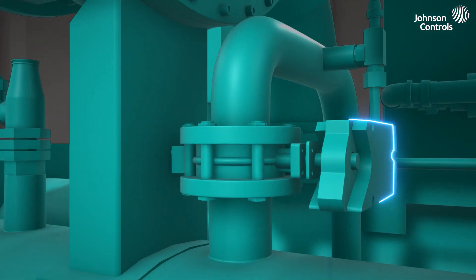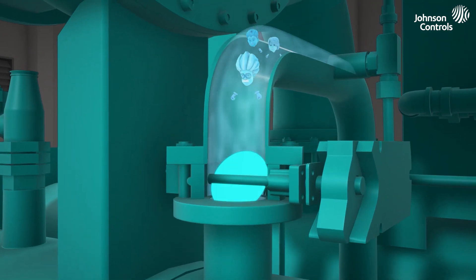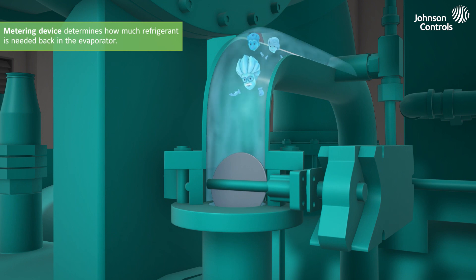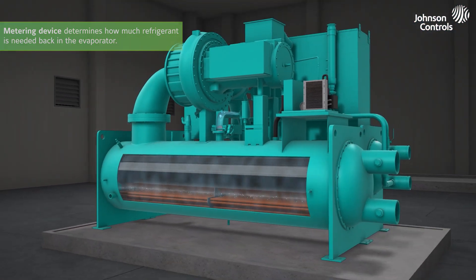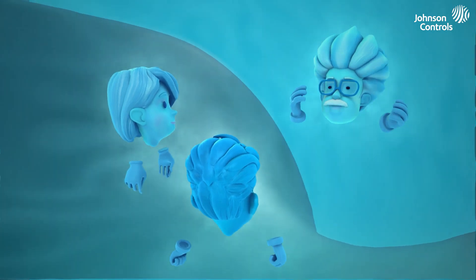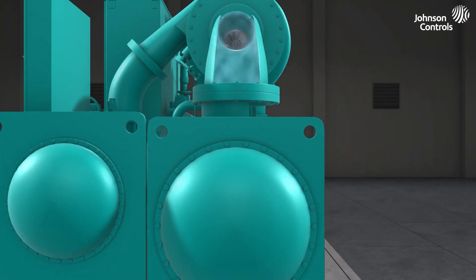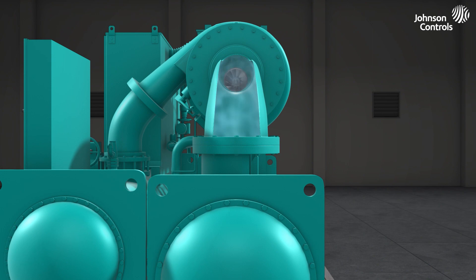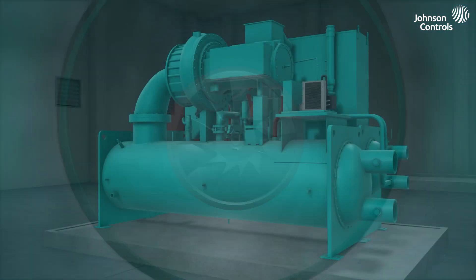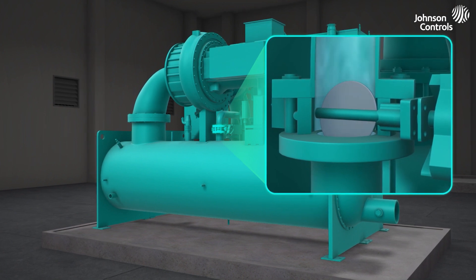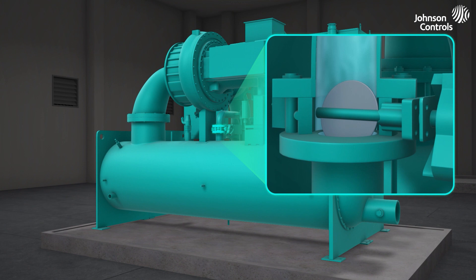This is where the metering device comes in. In addition to changing the pressure, the metering device, or expansion valve, is also responsible for determining how much refrigerant is needed back in the evaporator. Remember, we can't get any liquid in the compressor — if there's not enough heat in the evaporator to change us all to vapor again, then we'll have a problem. The metering device makes sure the right amount of refrigerant goes back into the evaporator and keeps everything running smoothly.